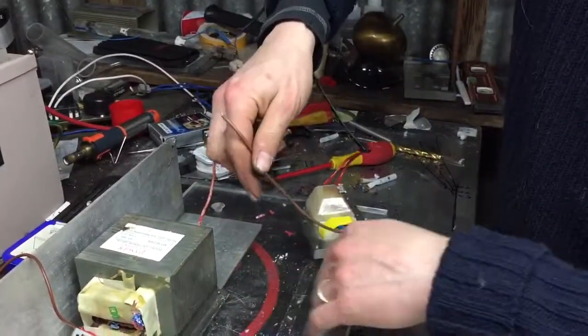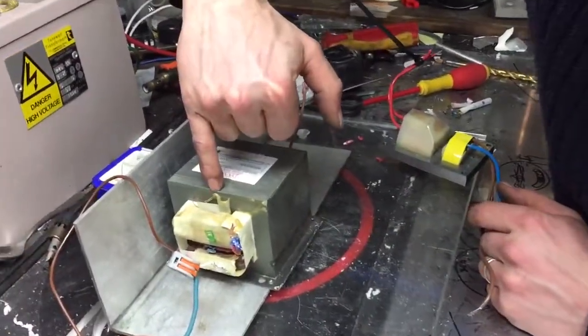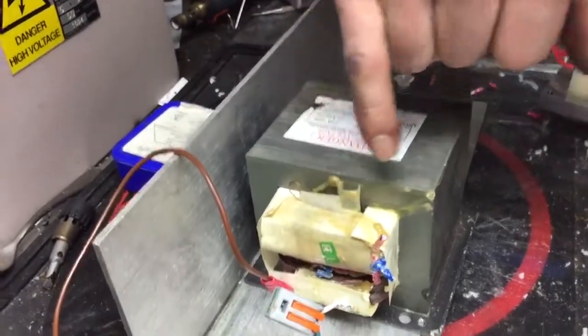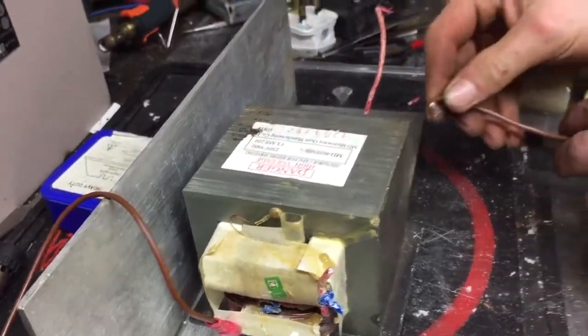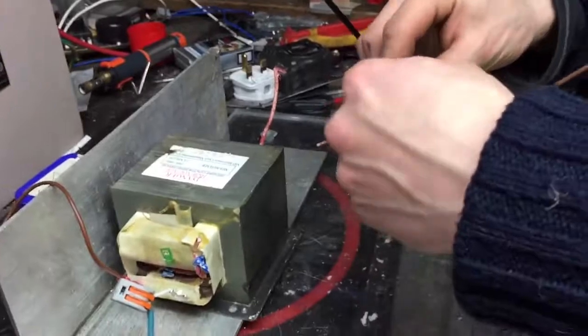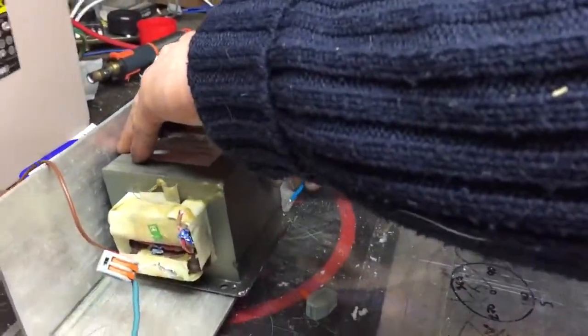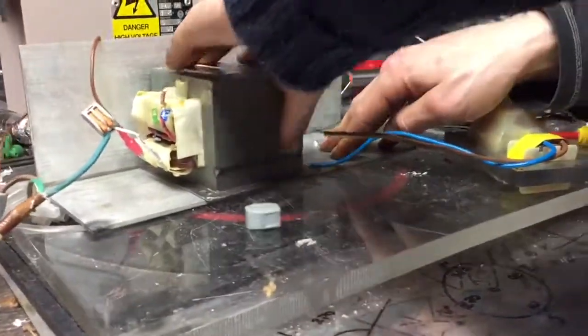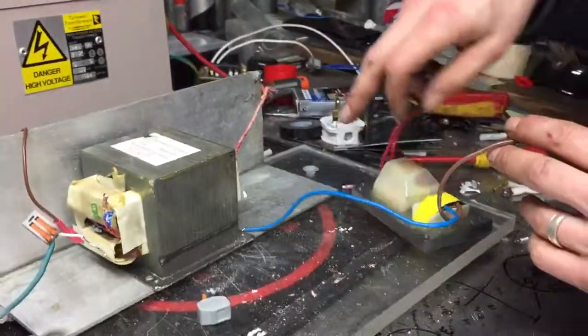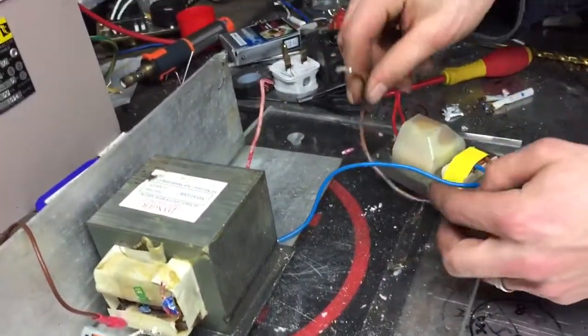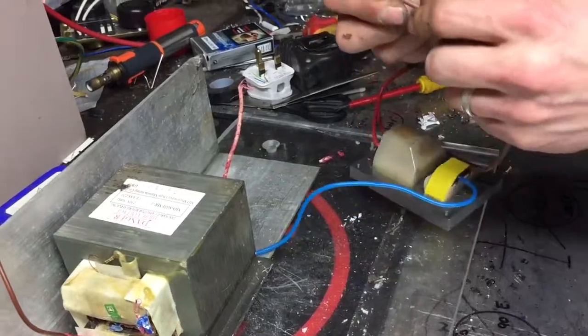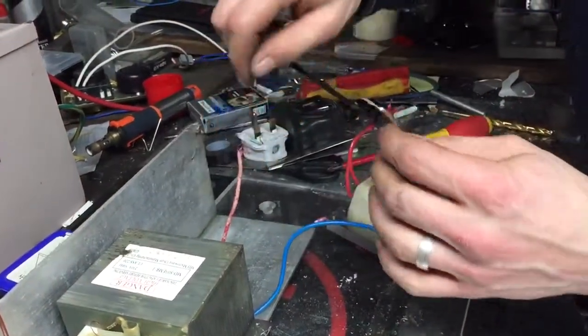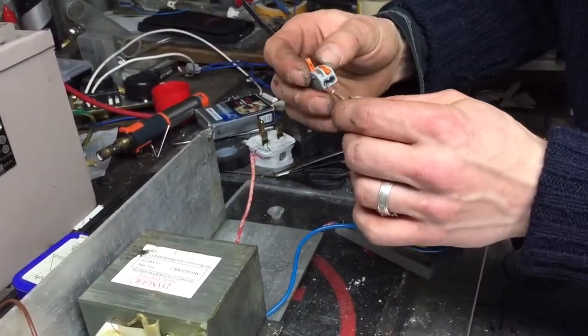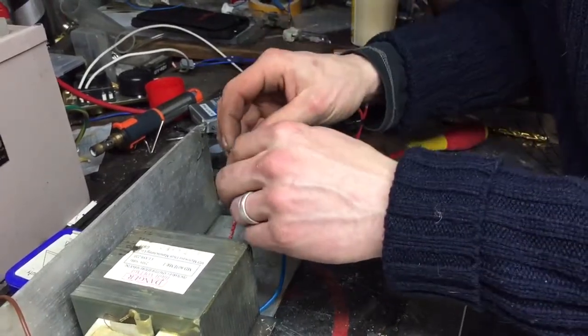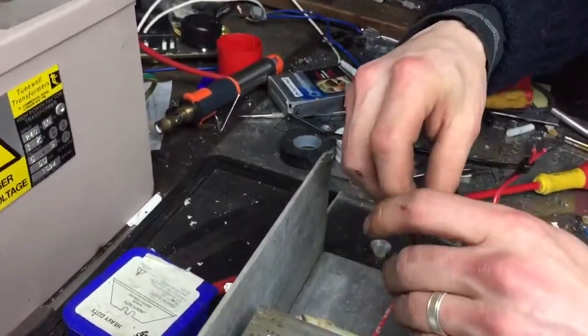This transformer here is one side grounded - as you can see, one side of the secondary coil is grounded to the case. So I've placed the transformer onto a piece of aluminium and I'm going to put this wire under there, so essentially the neutral is joined to the case of this transformer. I'm going to put the phase input onto here. We're using Wago connections because they're nice and easy and fairly safe - so into here like this.